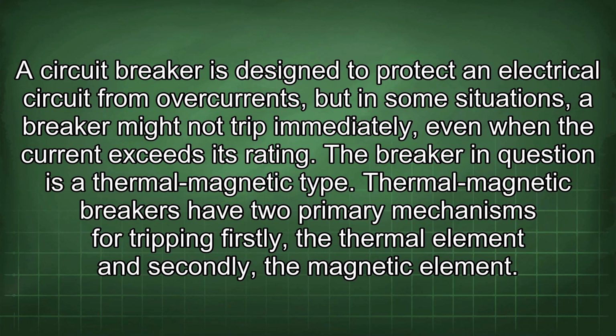A circuit breaker is designed to protect an electrical circuit from overcurrents, but in some situations, a breaker might not trip immediately, even when the current exceeds its rating. The breaker in question is a thermal magnetic type. Thermal magnetic breakers have two primary mechanisms for tripping: firstly, the thermal element, and secondly, the magnetic element.